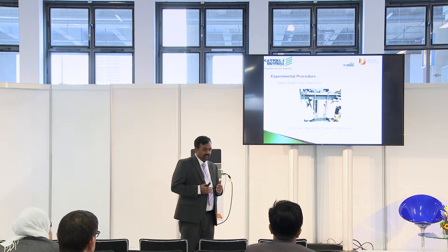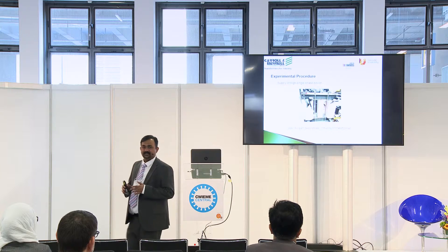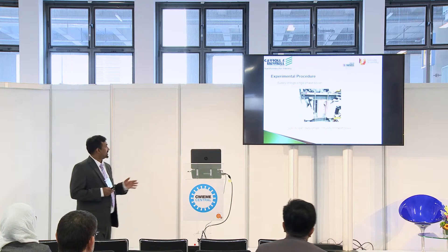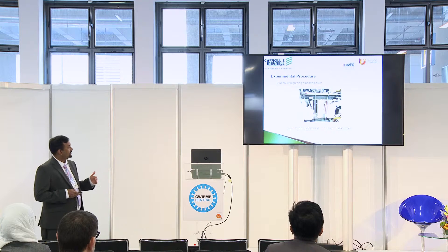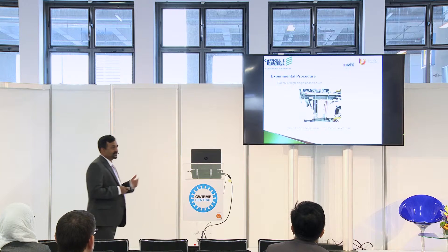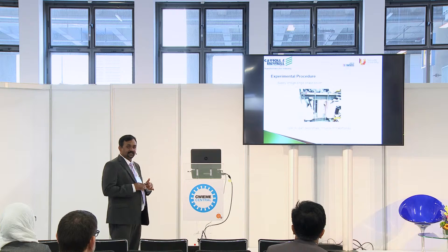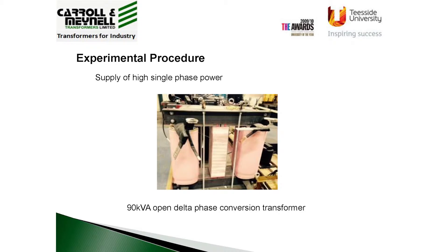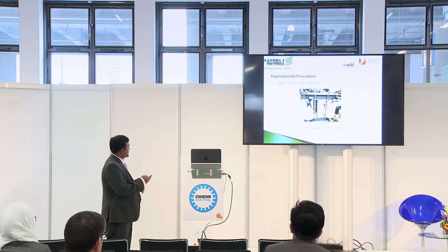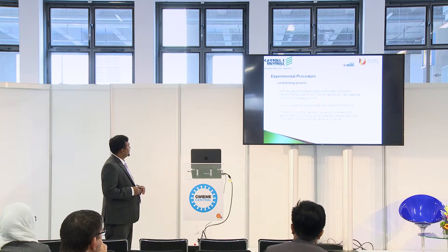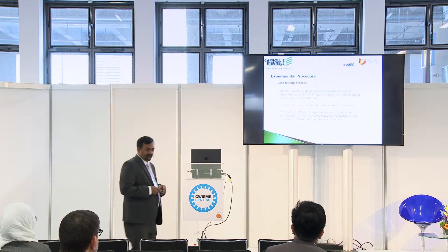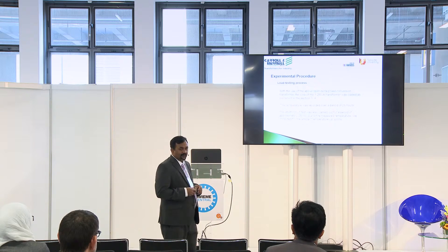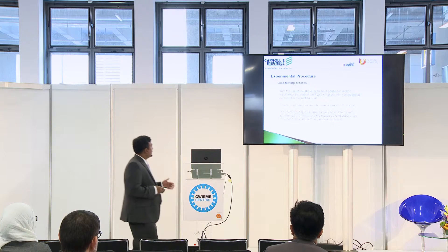Even with this technique, the transformer is quite large and drawing that power from a single phase supply causes an imbalance. Our solution was to construct a phase conversion transformer, sometimes called an open delta transformer — with a three-phase input you can get a single-phase output and it gives a reasonable balance to the input side. This is a picture of the transformer we constructed in this way.